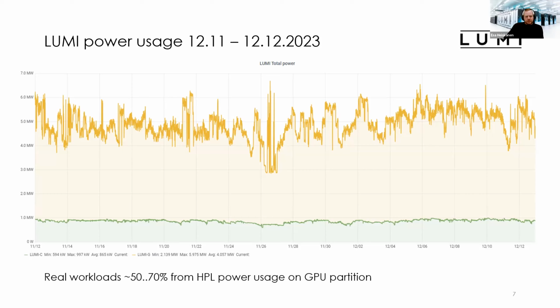These highest spikes here are from the hero runs that we did at the end of November, when the full system is drained and allocated for single users to allow them to run their big projects at the full scale of the GPU partition, so they are able to use the full capacity of our GPU partition for their workloads. And also in there, the high power swings are involved, like in the HPL. So when we are draining the system to the idle load, it is a little bit over 2 megawatts in the GPU partition, and then power swings up to 6 megawatts. So there are still those 4 megawatt power swings included in the operational period.